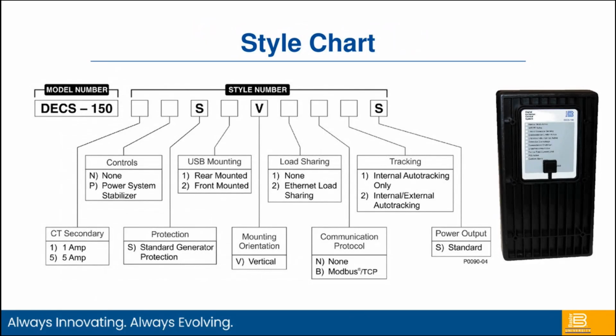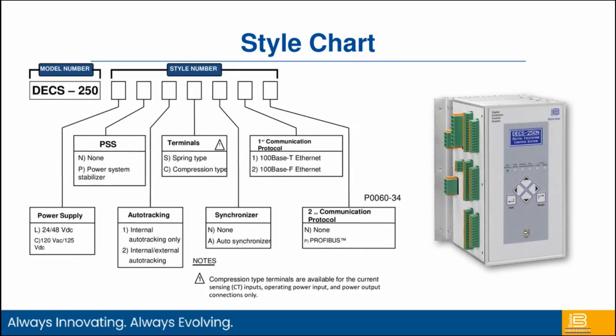As far as ordering, some options are style ordered, so not everything is available in every particular unit. In the case of the DECS, I think the big one is a 1 or 5 amp secondary input for the CTs. The PSS is an option in all of our models. And then your mounting configurations and how you want to set it up. So the style chart walks you through to make sure that the product you get meets your application and your intentions for use. 250 is very similar. 250 utilizes an external power supply, so we have to select that at either a 24 volt or a 125 volt power supply.